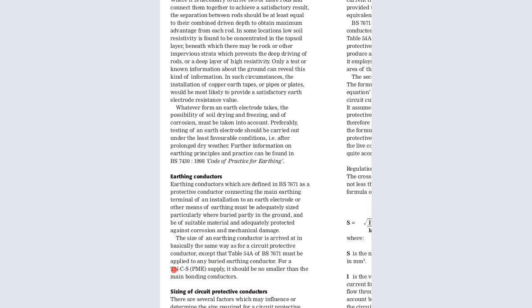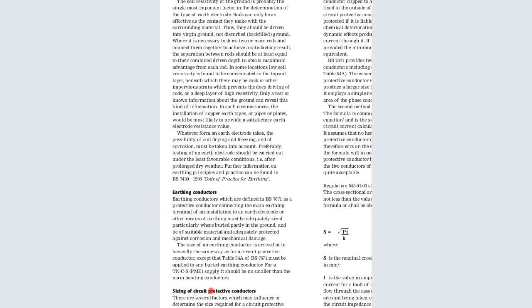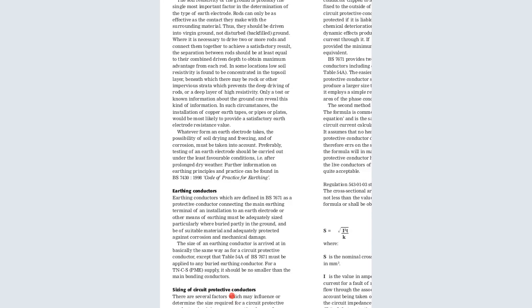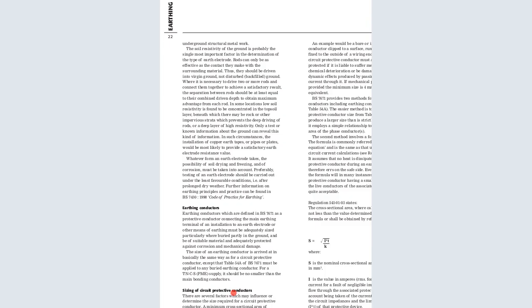So for a TN-C-S supply, it should be no smaller than the main bonding conductor. So the sizing of the circuit protective conductor, how do we size it? How do we calculate the sizing of the bonding conductor?